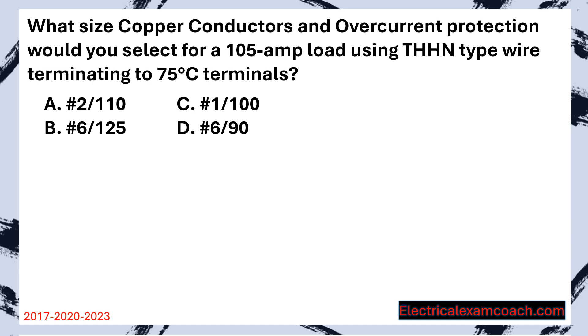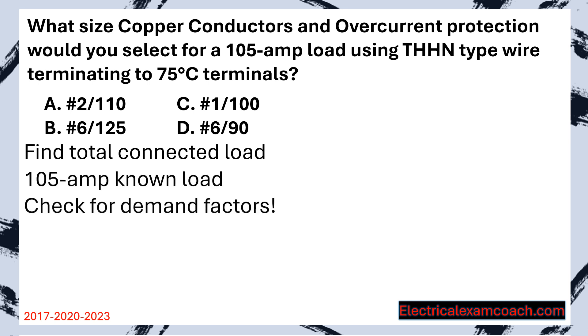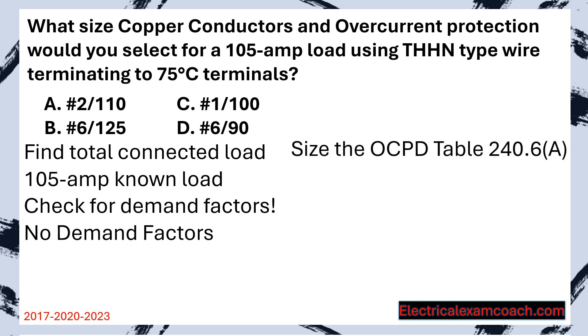What size copper conductors and overcurrent protection would you select for a 105 amp load using THHN type wire terminating to 75 degrees C terminals? Step one: find the total connected load — 105 amps, but we must check for demand factors. It doesn't mention a specific type of equipment or how many hours it's running, so there are no demand factors. We size our overcurrent protective device using table 240.6A. This is why it's very important to always go to the table and not just go off memory or what you might do in the field — out in the field you might say this needs to be on a 125 because 125 is a common number.